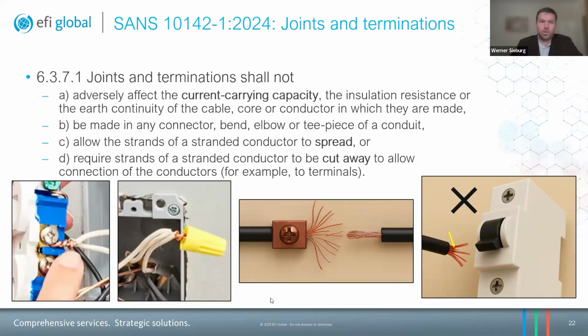Right, what not to do. Joints and terminations shall not adversely affect the current carrying capacity of the insulation or the insulation resistance or the earth continuity of the cable, core, or conductor in which they are made. Now, once again, I wish to point out that it is not a particular requirement of what you must do or what you must not do, but it is a requirement of outcome.